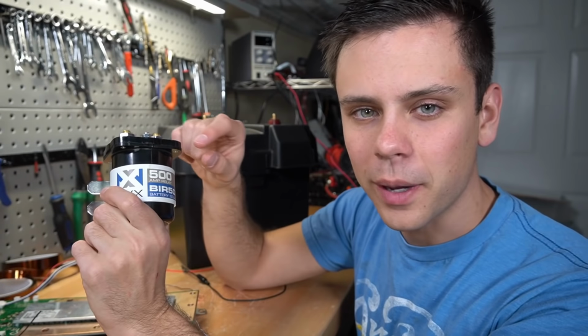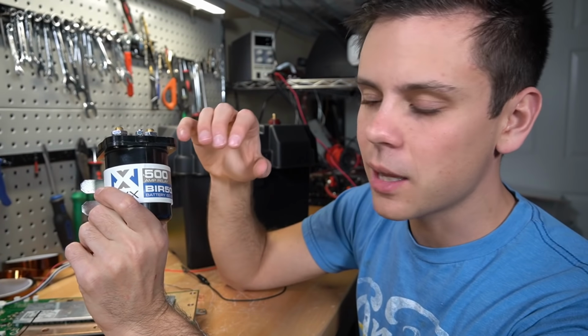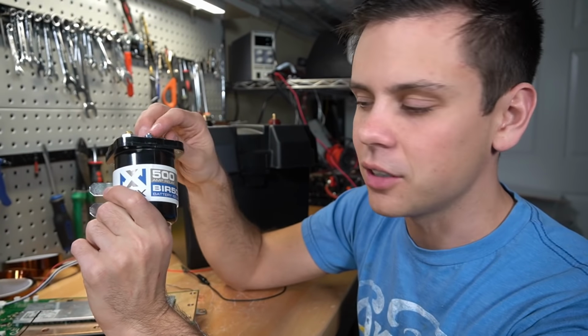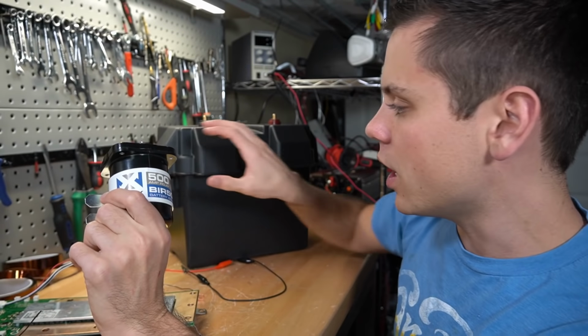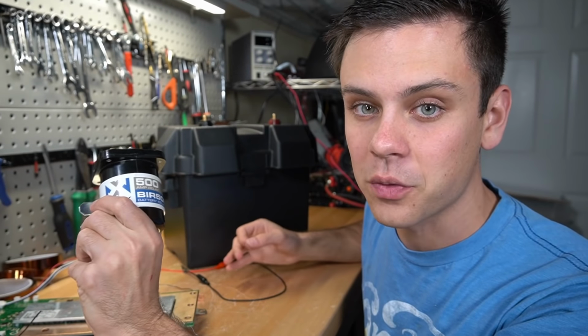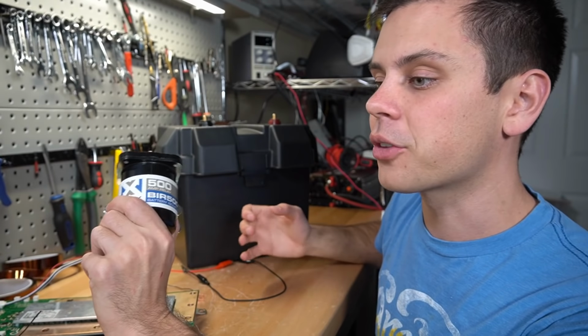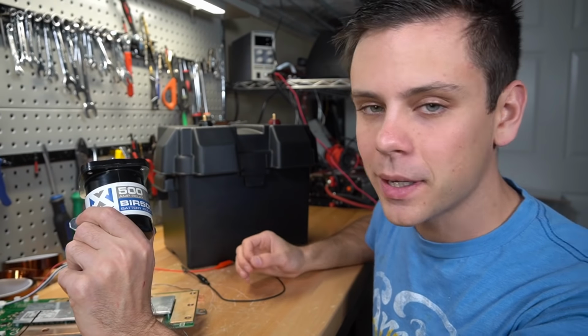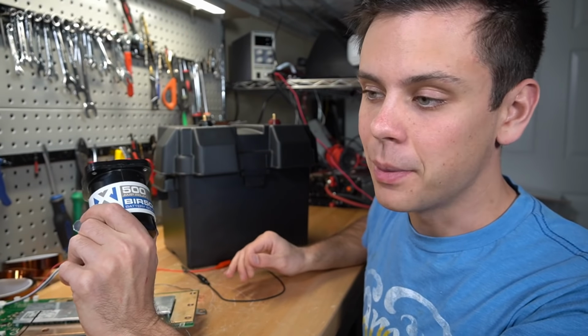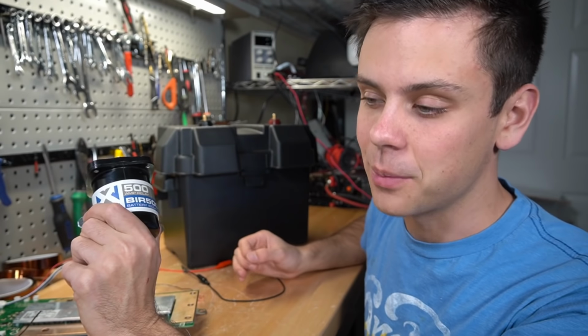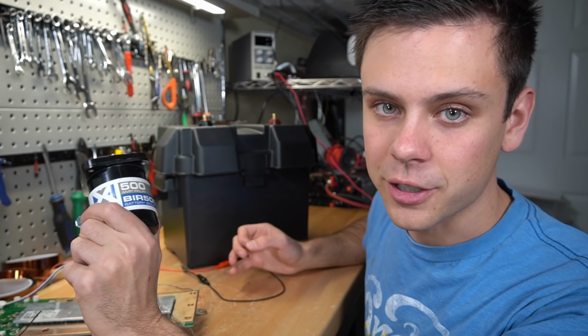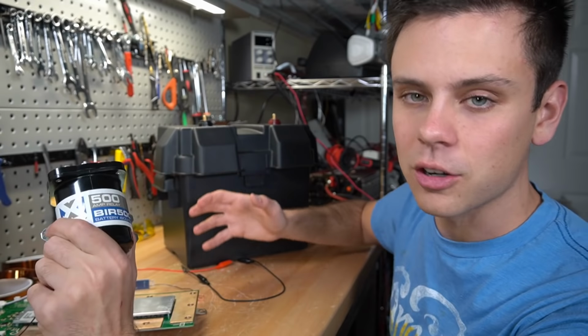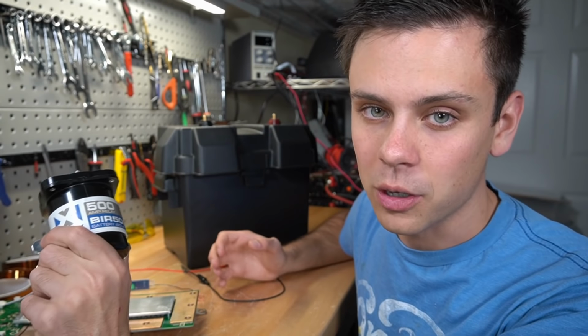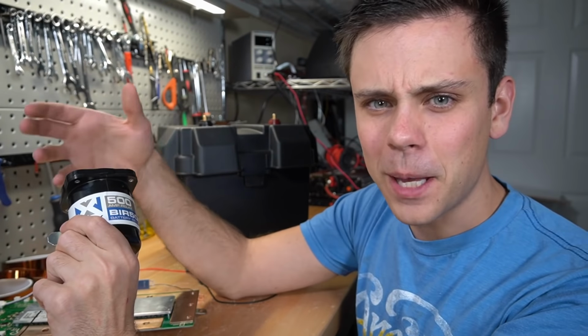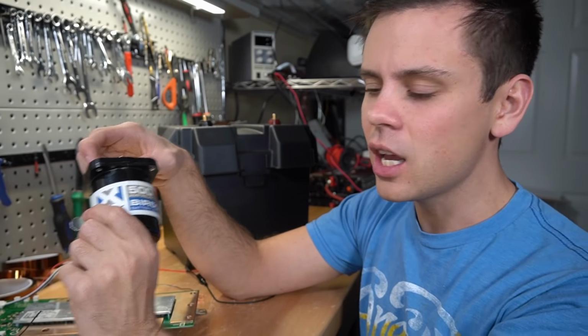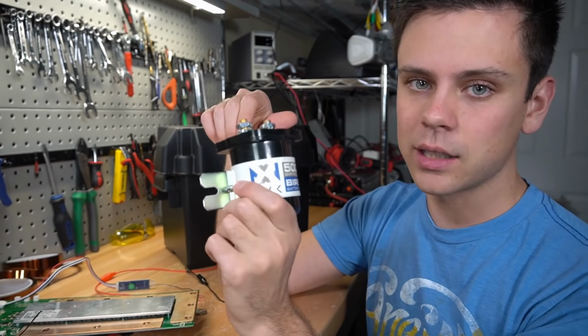What's really cool about using this large relay is that we can push our lithium iron phosphate cells to the limit. Typically, a 100 amp hour cell can handle a 3C discharge rate, that's 300 amps. If your BMS can only push 100 amps, but those cells can push 300 amps, you have a huge bottleneck on your system. If you want to power very large loads on an inverter with a smaller battery, or you can't find a BMS with a high enough current rating, you can easily use a relay to run that load.